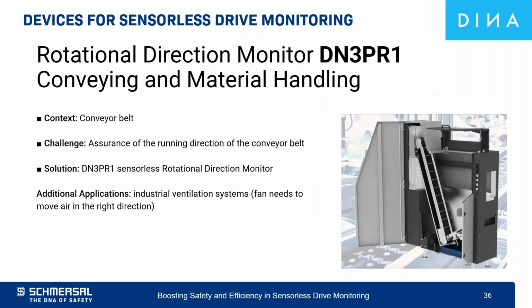Okay, what is a typical application? Rotational direction matters when it comes to conveying and material handling. So, for example, with a conveyor belt, to assure that it is running in the correct direction, the DN3PR1 can be used. Other applications would be industrial ventilation systems. So here you also need to assure that they move the air, for example, in the right direction. This is very important.